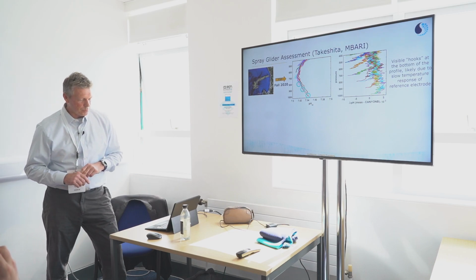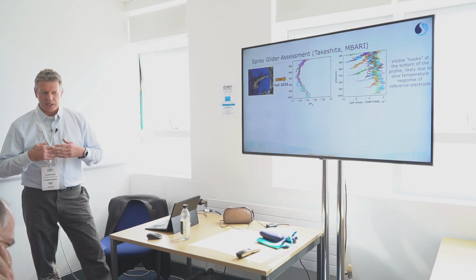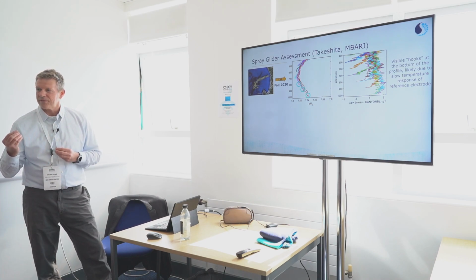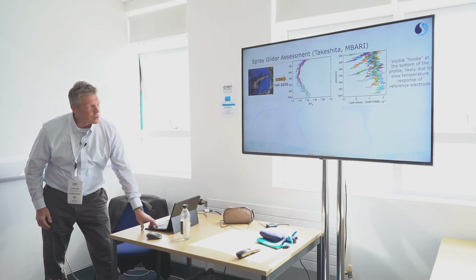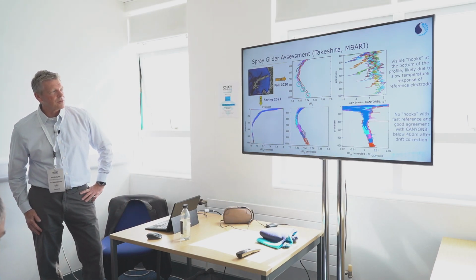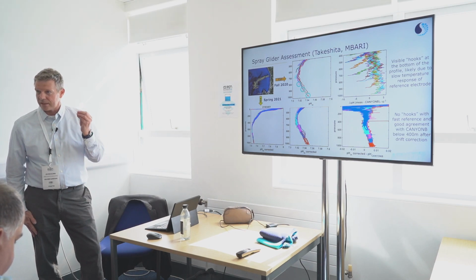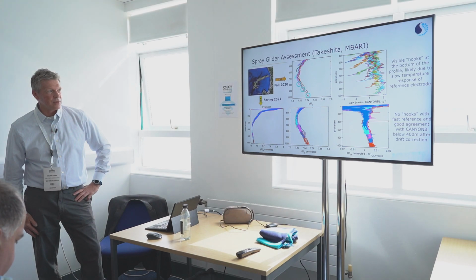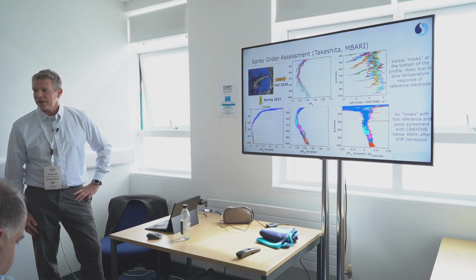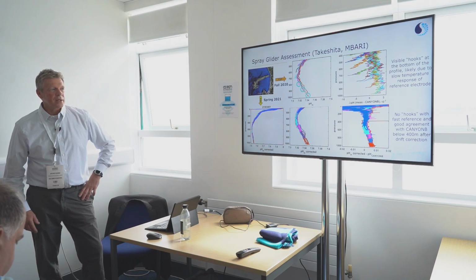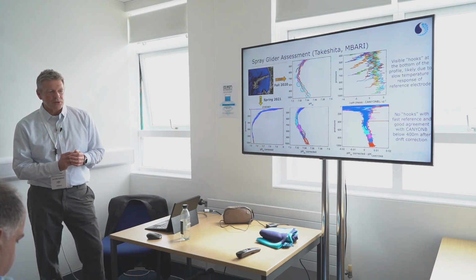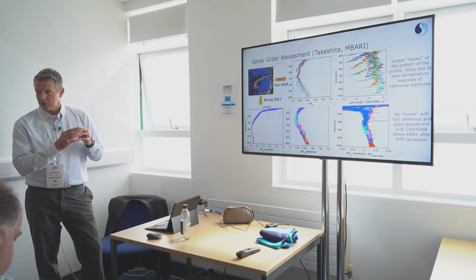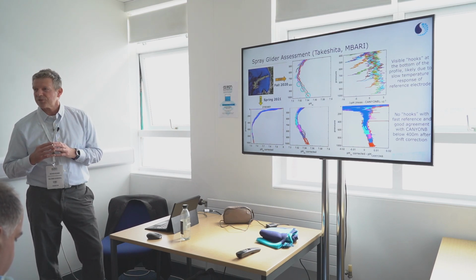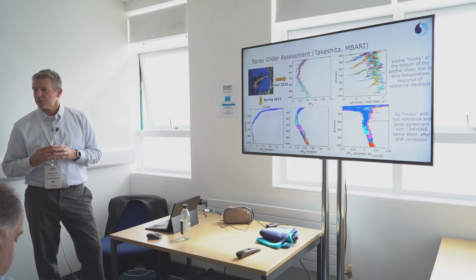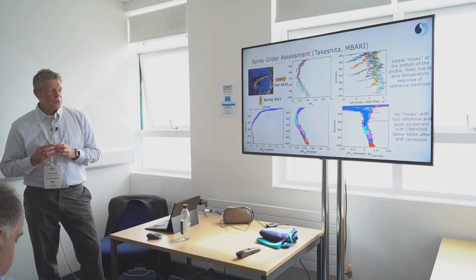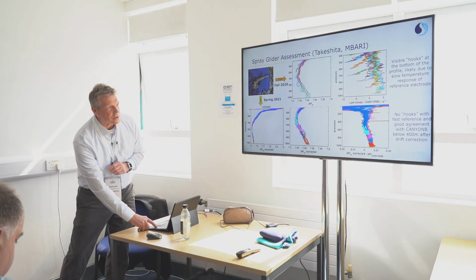So we evaluated what happens if we change the reference electrode to a faster one. We did another deployment of gliders with a faster reference, the same ISFET sensing element, but a faster reference, and the hooks disappear. So we have the additional challenge of not only having a very tight tolerance design on the ISFET sensing technology, but also batch-to-batch variability on the reference side that we have to account for when we calibrate the sensors. This is where I wanted to stop.